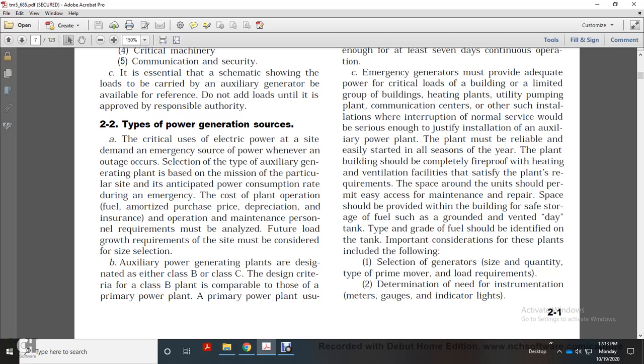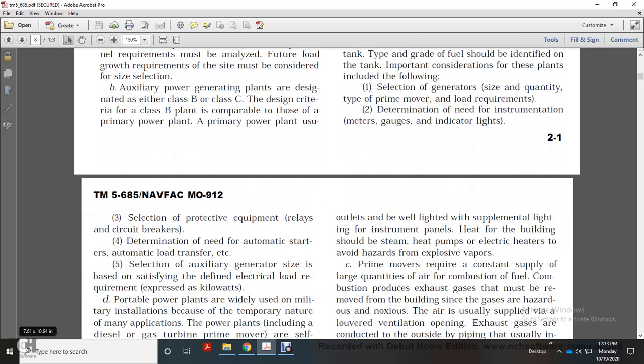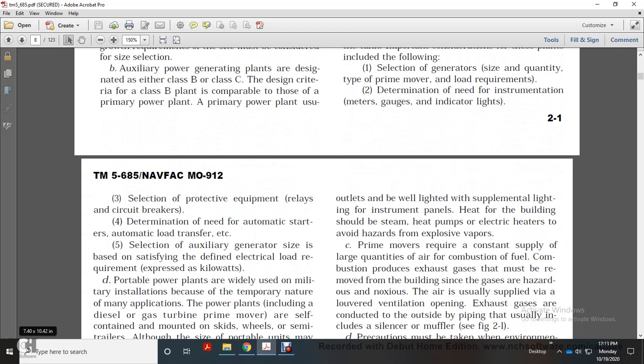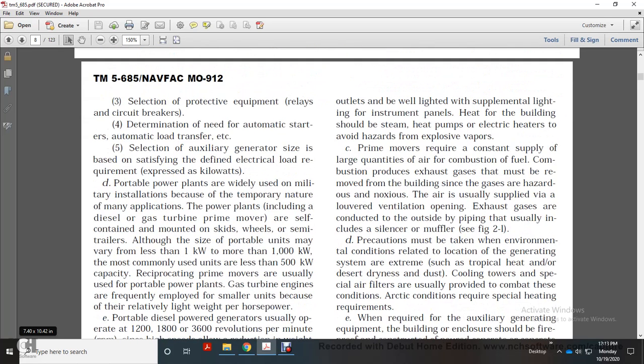Plant design includes the following steps: (1) Selection of generator size, quantity, type, and prime mover based on load requirements. (2) Determination of the need for instruments, meters, gauges, indicators, and lights. (3) Selection of protective equipment, relay circuit breakers. (4) Determination of the need for automatic start and automatic load transfer. (5) Selection of auxiliary generator size based on defined electrical load requirements expressed in kilowatts.